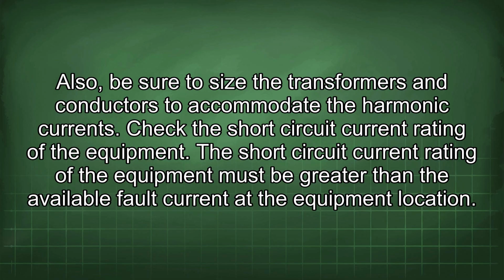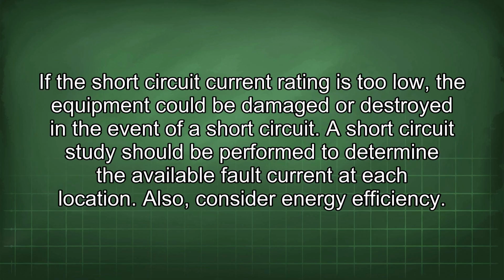Check the short circuit current rating of the equipment. The short circuit current rating of the equipment must be greater than the available fault current at the equipment location. If the short circuit current rating is too low, the equipment could be damaged or destroyed in the event of a short circuit. A short circuit study should be performed to determine the available fault current at each location.